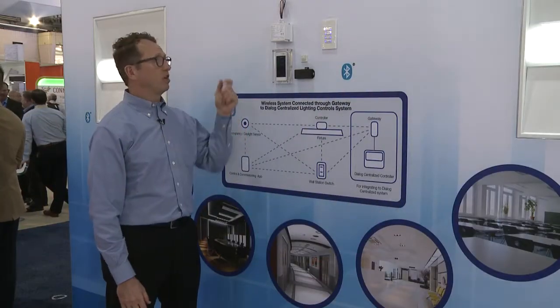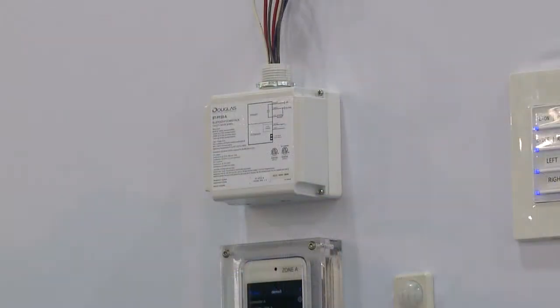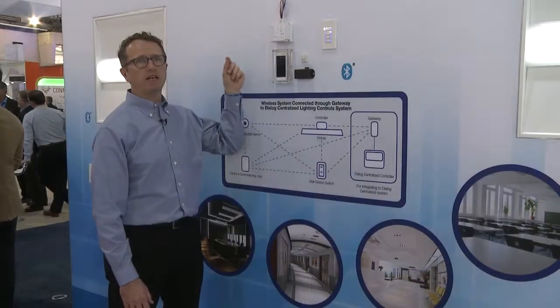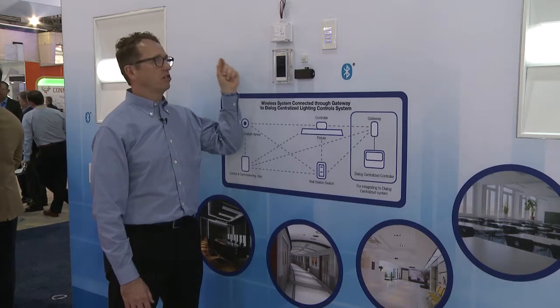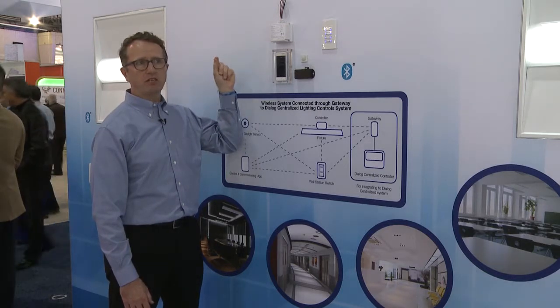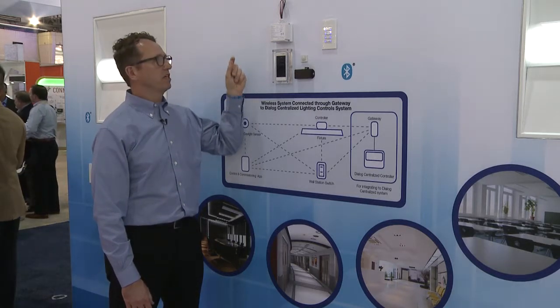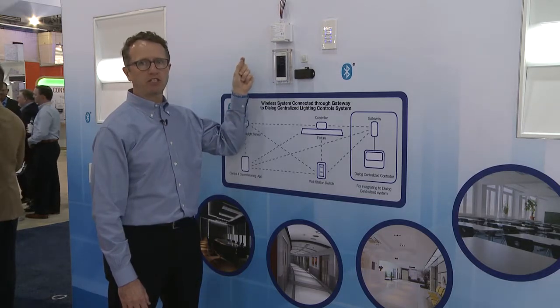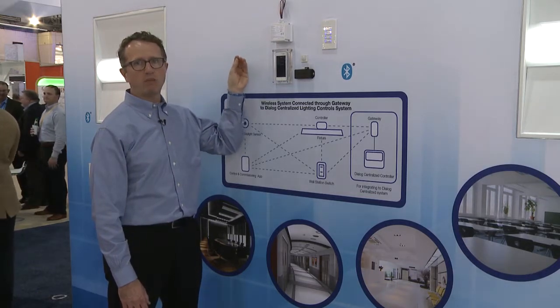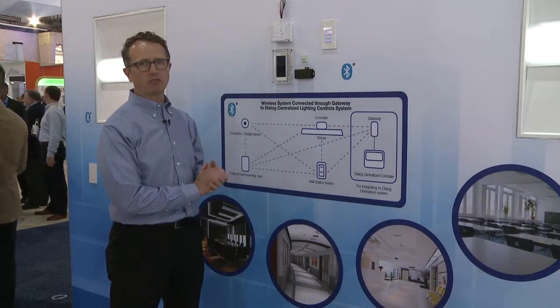Our wireless system starts with the power pack. It has a 20 amp relay and also provides 0 to 10 volt dimming, and has a Bluetooth chip in it, so it communicates to other devices in that Bluetooth network. You'd attach this power pack to a fixture or a number of fixtures to one power pack, and that gives you the base of controls.